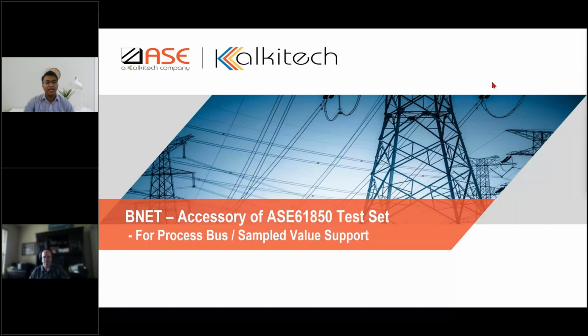BNET is an accessory basically for the ASE61850 test set. Currently, the ASE61850 test set supports MMS and GOOSE. Basically, it covers all the station bus functionalities. But right now, it doesn't support the process bus functionality or the sample value. With BNET, it will be an accessory to the ASE61850 test set so that it can support sample value. So that's the primary goal of the BNET hardware.